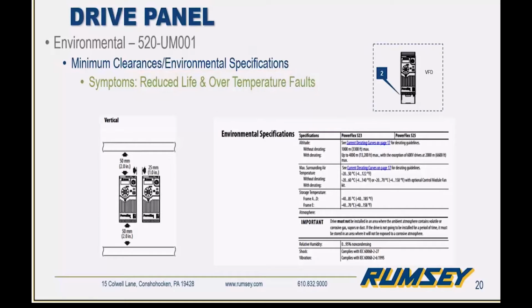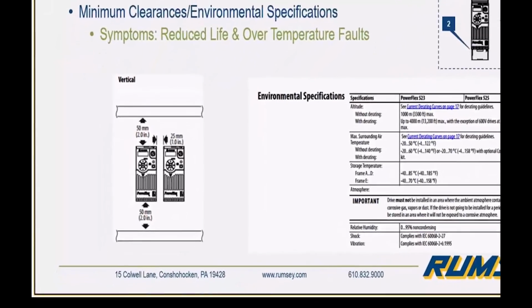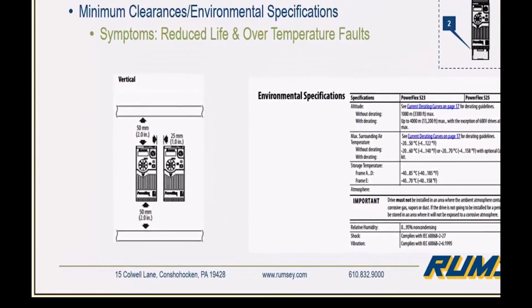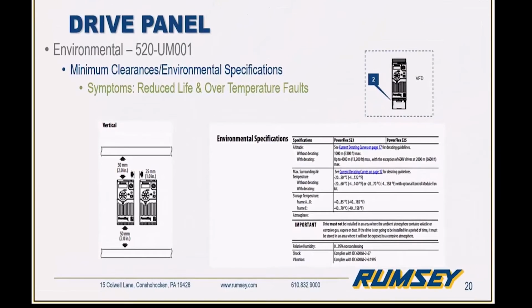But what is most often overlooked is the minimum spacing requirements. On the lower left here, we have an image from the PowerFlex 520 series installation manual, or user manual. It clearly states that the drive needs a certain amount of space above and below the drive, and the main reason for that is to provide adequate airflow. So if we have anything between or closer to the drive than what's recommended, we're going to end up restricting the airflow, and airflow is the most critical part for providing cooling for the drive.